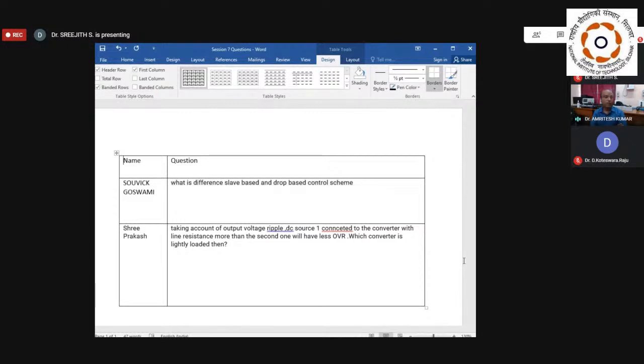But obviously in the master-slave configuration, the thing is that you require information. A communication line is required to know how much each one has to share. But in a droop-based control, basically all are masters. And if you have multiple synchronous generators in the system, how are they going to stabilize the frequency and the voltage?